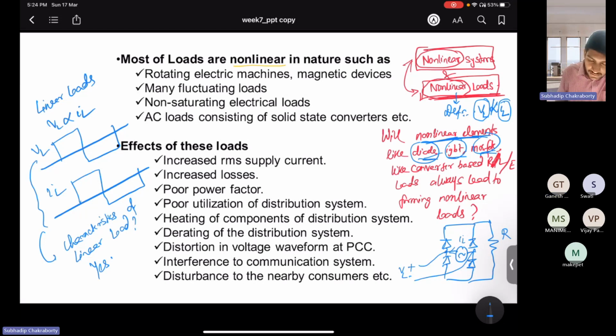After understanding what a nonlinear load is, let us go ahead with a brief overview of the nonlinear loads. What are their impacts? Impacts I already told you. The nonlinear loads lead to an increment of the RMS current in the line. And if you have a higher current flowing in the line for the same amount of power that you have to transfer, then it obviously leads to loss in the AC lines, because you have resistance, and that loss is I RMS square into R, because R line, the feeder resistance, is constant. But for the same amount of power to be transferred for these dominating nonlinear loads, this I RMS increases. So due to the increase in the amplitude of I RMS, or due to the presence of harmonics, we have more I RMS in magnitude. That's why it results in loss in the line.